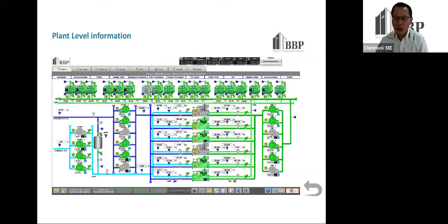What we do is we install these small boxes on the chillers, with temperature sensors and flow meters, the parameters we need in order to understand the current performance of the system. We feed this data to our controller, and the controller processes it and comes out with the optimum operating parameters to modulate, to make the system more efficient and to sustain the performance level.